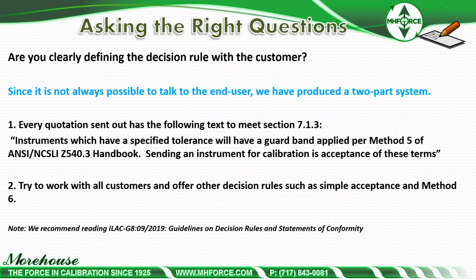So if you're not, since it's not always talk to the end user, we personally have done a two-part system. Part one, every quotation out has this: instruments which have specified tolerance will have a guard band applied per method 5 of ANSI Z540.3 handbook. Sending an instrument in for calibration is acceptance of these terms. This is on every quotation that we send out. Try to work with all customers and offer other decision rules, such as simple acceptance and method 6. Hey, we can do that.